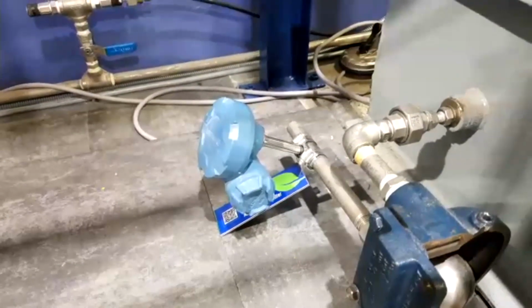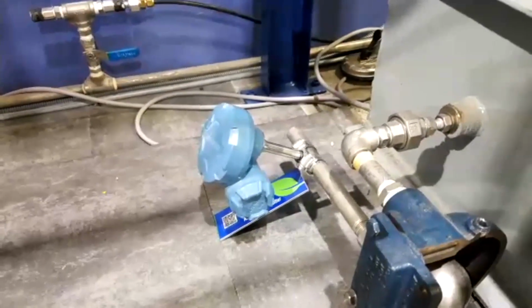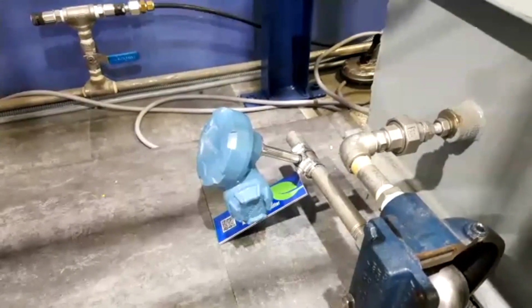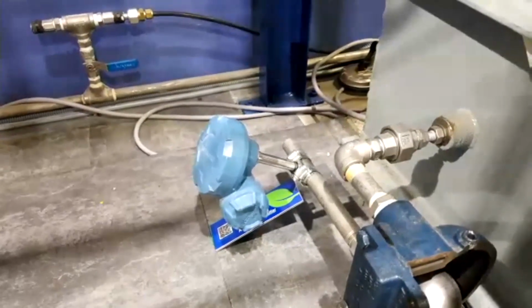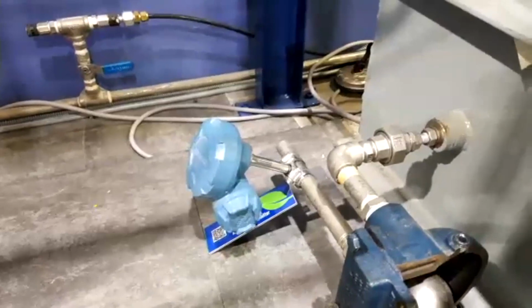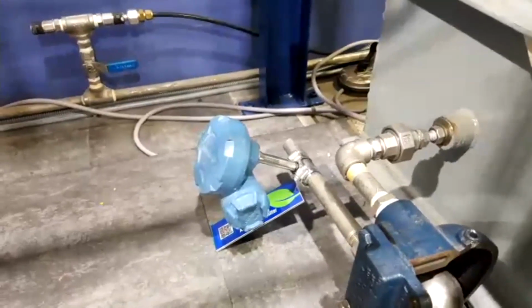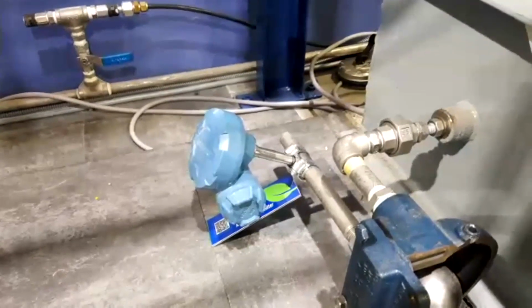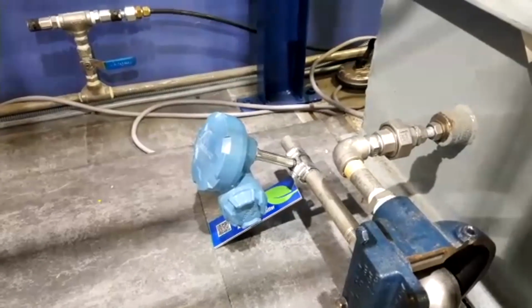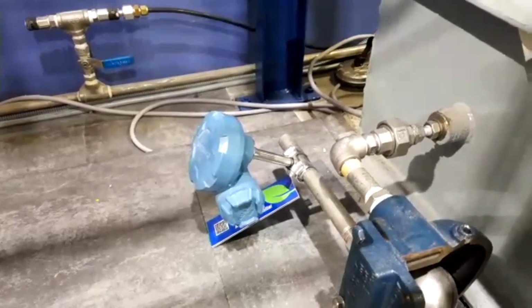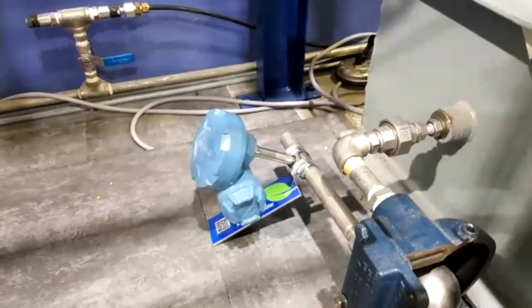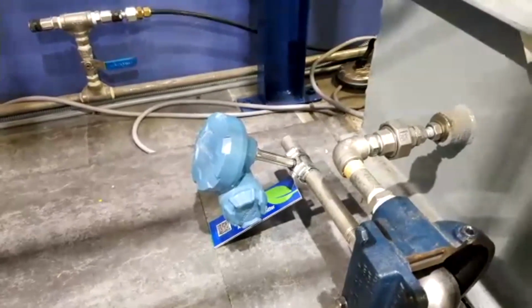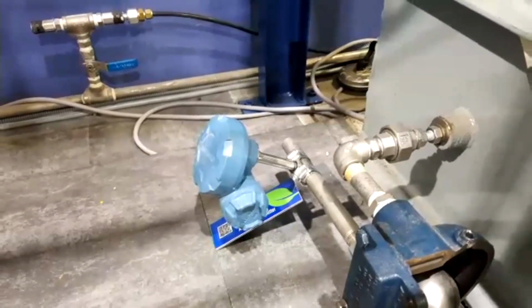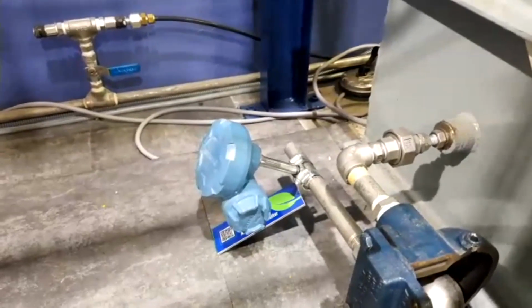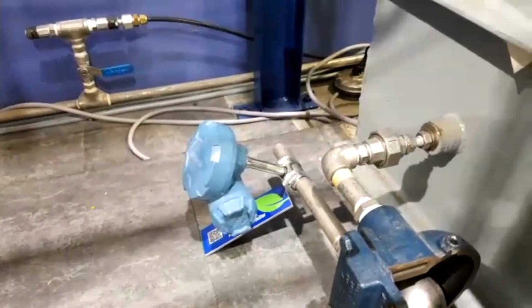So instead of the steam trap blowing steam for maybe 6 months or a year, you can replace it immediately, reducing steam loss. The analytics use the acoustic and temperature data to determine the health of the steam trap, whether it's blowing steam, trapping condensate, or functioning well. It really works for any type of steam trap.